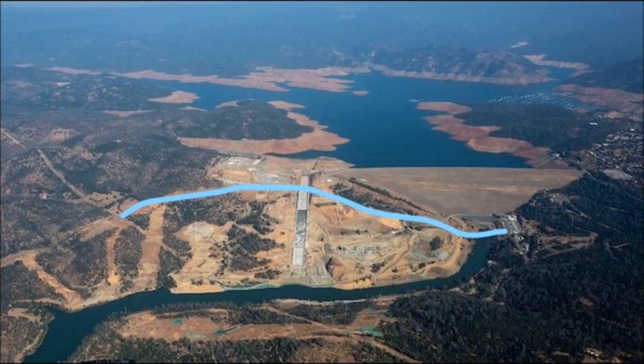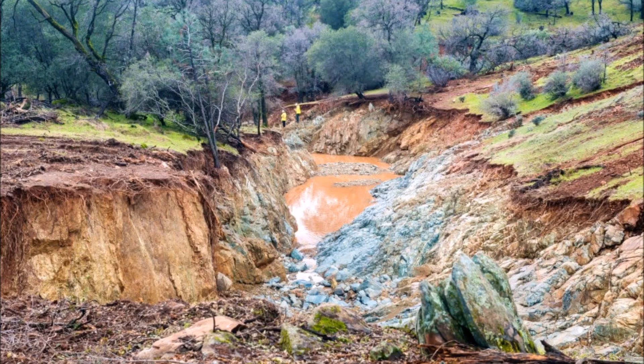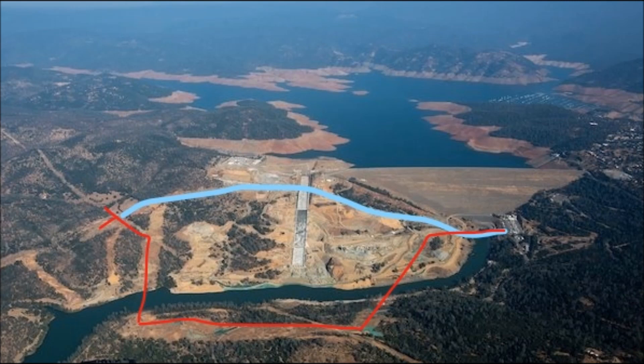The original transmission lines from the Hyatt Power Plant went right over the main spillway and the face of the emergency spillway. During the emergency, erosion from the emergency spillway threatened the footings of these power lines, so the lines were cut and dropped to the ground. Without the Hyatt Power Plant connected to the grid, it can no longer operate and can no longer flow water out. The better long-term solution is to reroute the transmission lines completely around both spillways. First, crews had to build a shoofly — a temporary connection along the existing transmission line — to get the Hyatt Power Plant reconnected to the grid, then disassemble the existing towers, move them to new locations, string the new wire, and remove the shoofly connection.